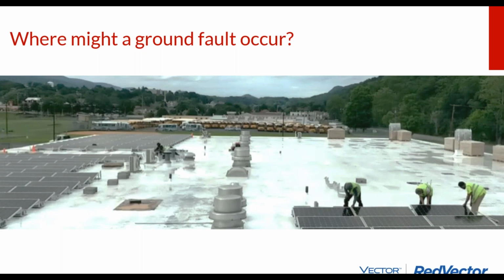I don't know if on those rooftops the solar array is the smartest idea, because if those connectors are droopy and they droop down onto that roof deck and then they get full up with water, you have metal connecting the solar array to ground. And so just a connector on a roof deck in the rain full of water can cause a ground fault. So you do have to approach particularly commercial solar very cautiously and have good cable management all the way through.